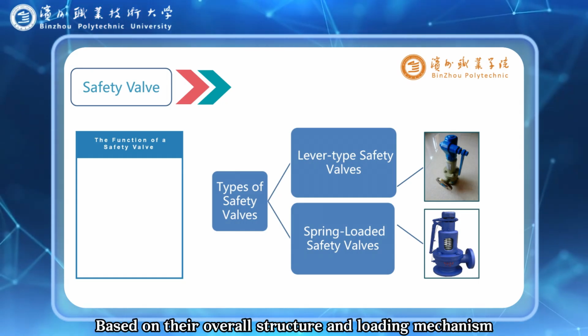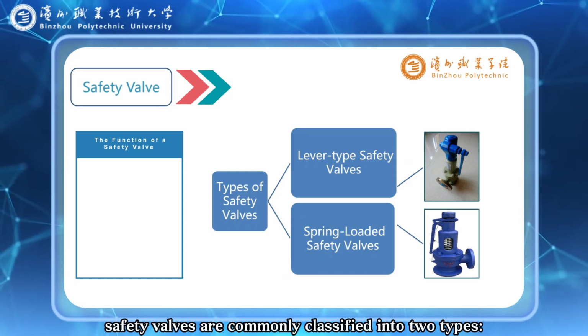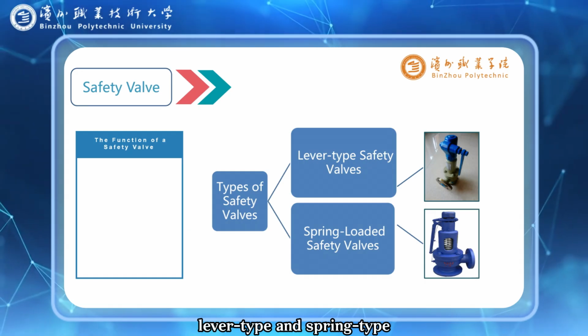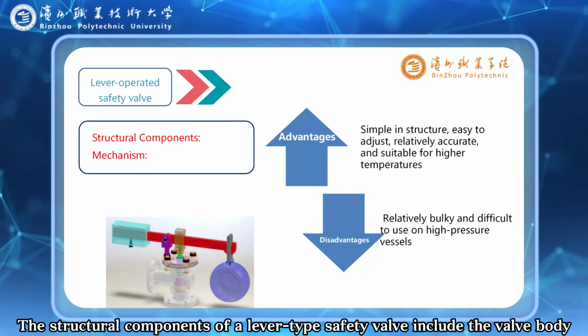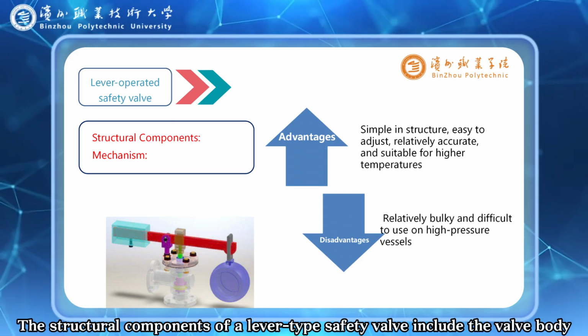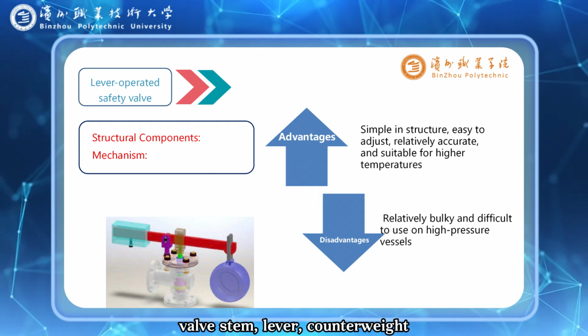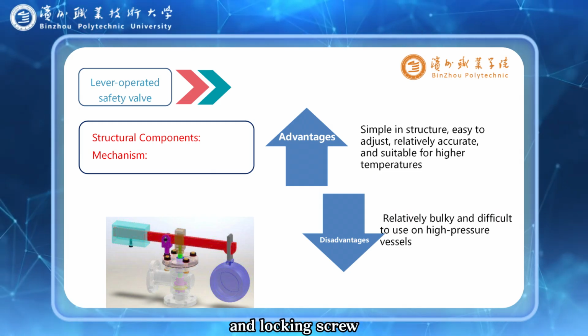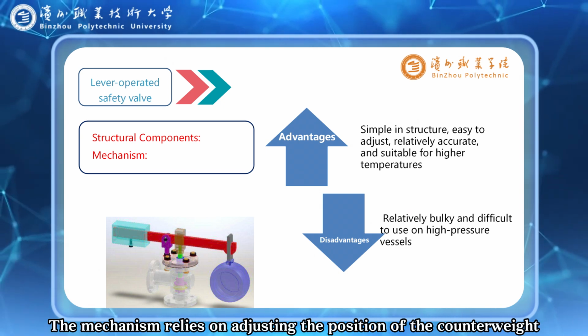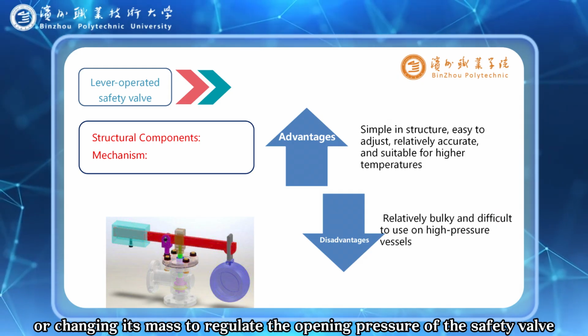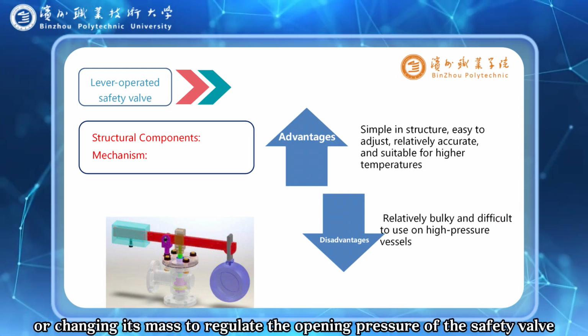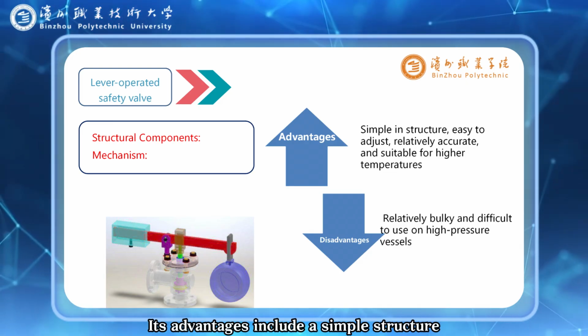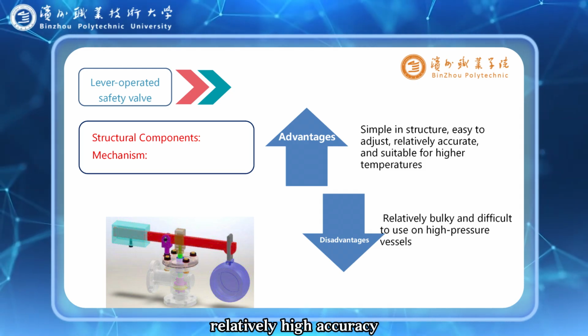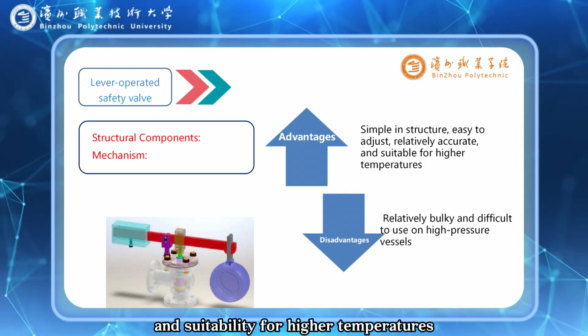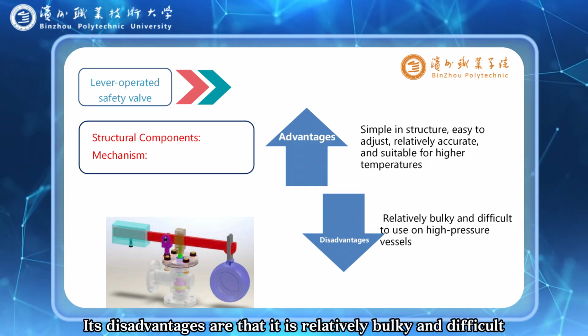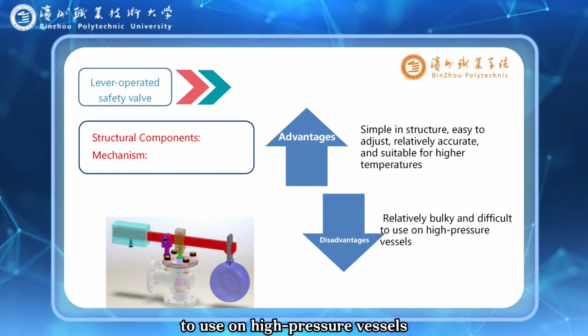Based on their overall structure and loading mechanism, safety valves are commonly classified into two types: lever type and spring type. The structural components of a lever-type safety valve include the valve body, valve disc, valve stem, lever, counterweight, adjustment screw, and locking screw. The mechanism relies on adjusting the position of the counterweight or changing its mass to regulate the opening pressure of the safety valve. Its advantages include a simple structure, convenient adjustment, relatively high accuracy, and suitability for higher temperatures. Its disadvantages are that it is relatively bulky and difficult to use on high-pressure vessels.